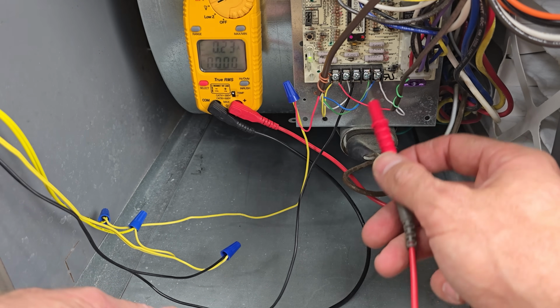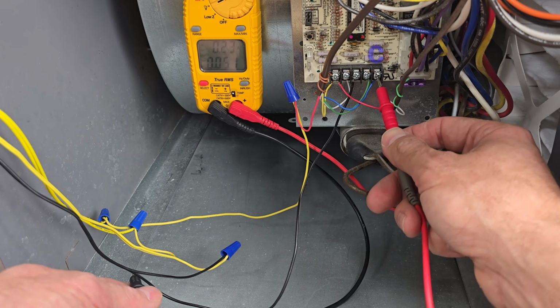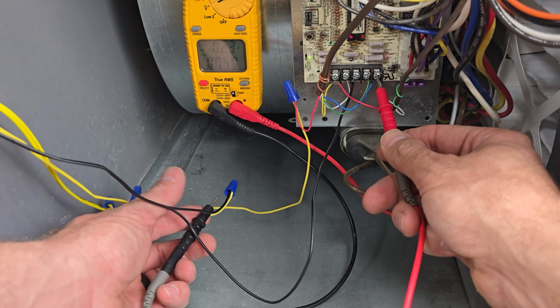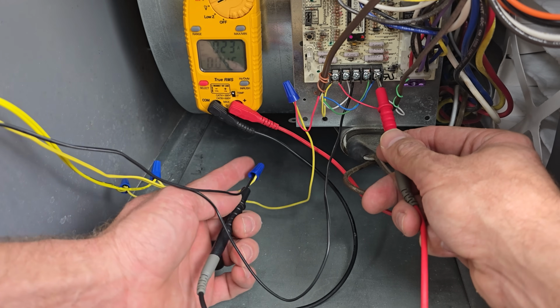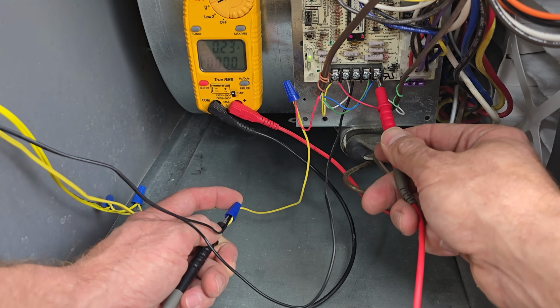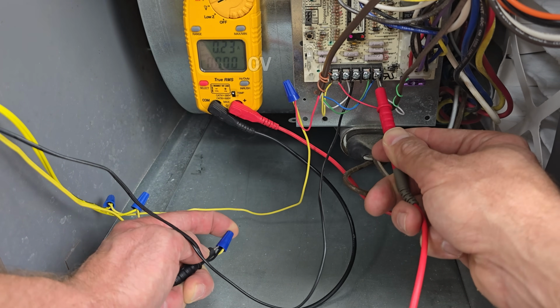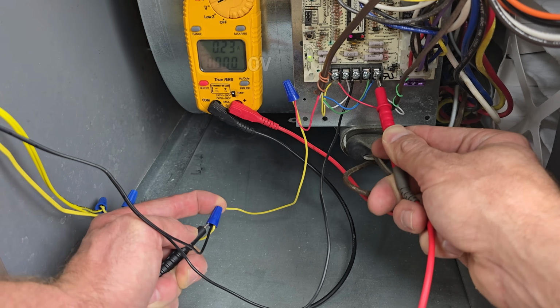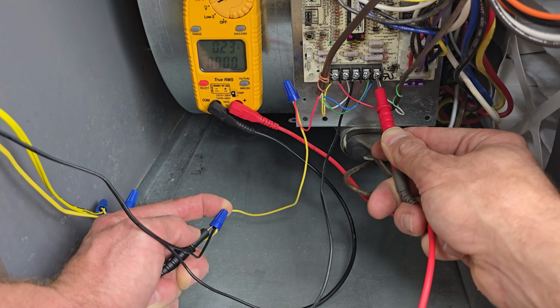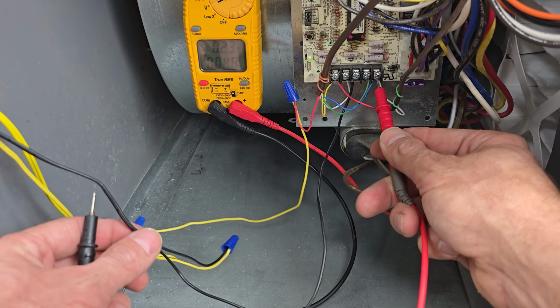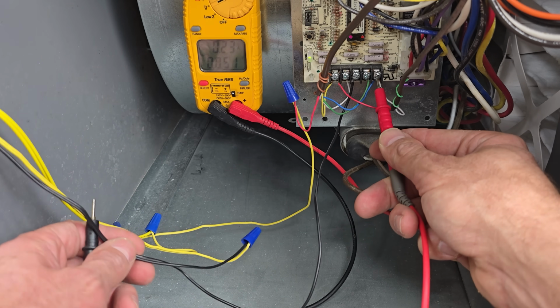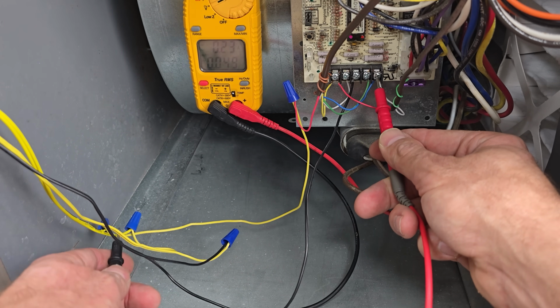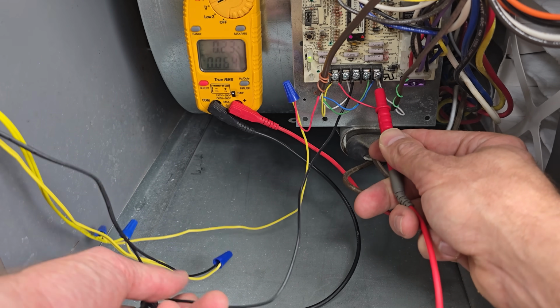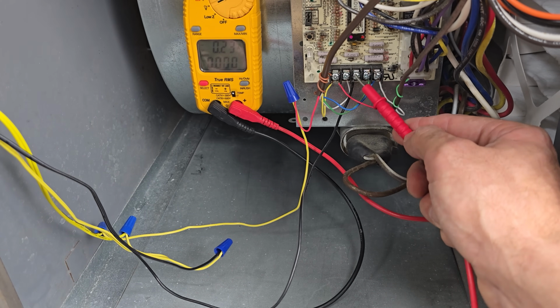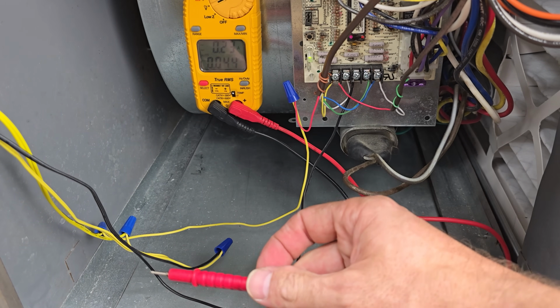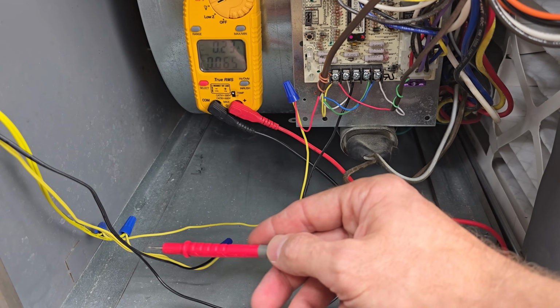Now we're going to measure for voltage, so we're going to put one probe on the common, or even the ground for that matter, and we're going to put the other probe into this wire nut, and we see that we measure 0 volts still. So that's telling us that the switch that's connected to these black wires is the problem. Now, we may have an additional problem once we fix that on one of the other switches as well, but since this wire is the one that's going into the R, it's going through this black wire into the switch and then out of the switch and over to here.